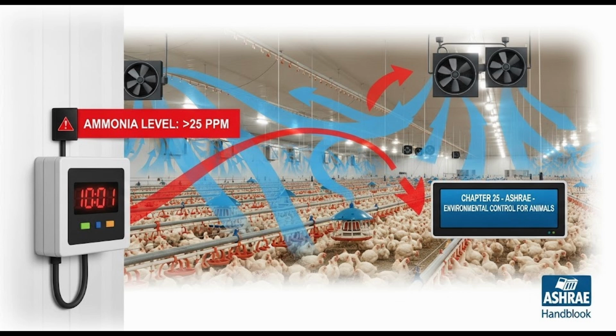Second is air cleaning, using filters or scrubbers. But this is mostly practical and economical for removing particulates, the dust. Gas removal systems are generally too expensive for large animal facilities. But dust filtering helps. It can, but filters need maintenance and add resistance to fans.